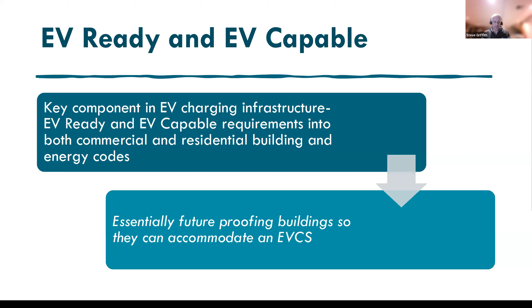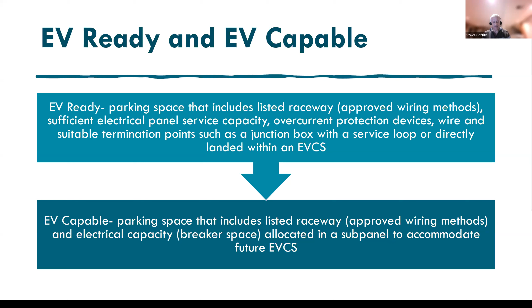Next slide. EV-ready is basically a parking space that includes a raceway, electrical panel service capacity, overcurrent protection devices, wire, and termination points like a junction box with a service loop, or one that's landed within an EVSE. EV-capable is a parking space that has a raceway allocated and a sub-panel to accommodate future EVSE installations, but not the EVSE itself.